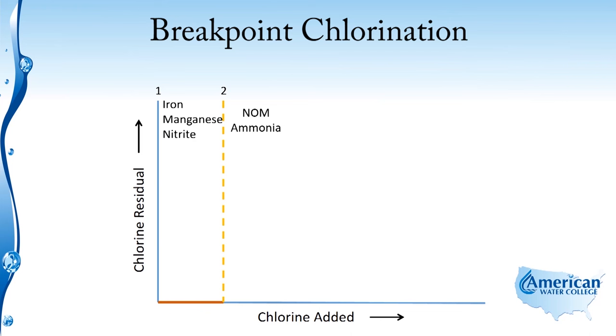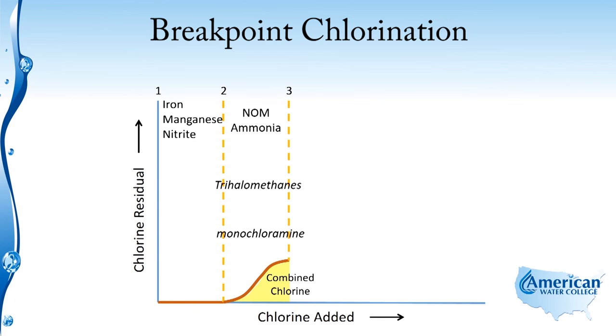Once that demand has been met and we continue adding chlorine, it's going to react with the natural organic matter and the ammonia in the water between points two and three, and form combined chlorine — which is for the most part monochloramine. Also between points two and three, this is where trihalomethanes are formed due to the reaction between chlorine and natural organic matter. At this peak, we have a chlorine to ammonia nitrogen ratio of five to one.